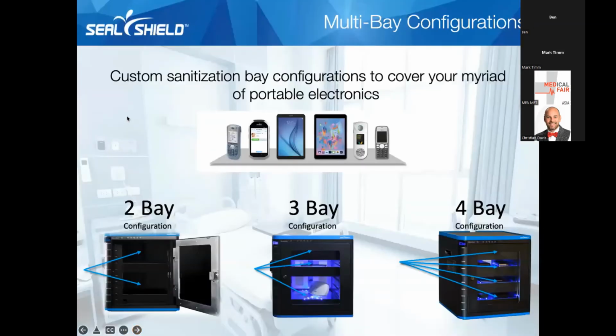So the electroclave has multiple configurations beyond being scalable from an enterprise standpoint. It comes in a 2-bay, so 2 disinfection bays, 3 disinfection bays, or 4 disinfection bays. These are all configurable because hospital systems have different mobile devices or handheld electronics that they need to disinfect. Sometimes they need 2 large bays and a 2-bay, or in other cases, they need 1 large bay and 2 small bays for mobility. Or it's strictly that they're trying to disinfect mobility, so then they want 4 bays in their electroclave. So multiple configurations to help the customer really tailor the solution to get after disinfecting the electronics that are of concern to them.